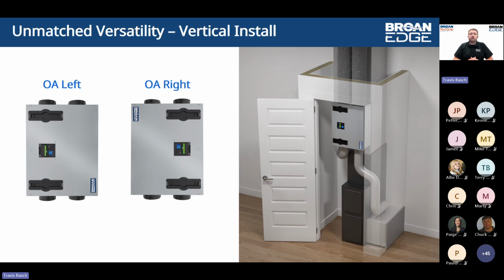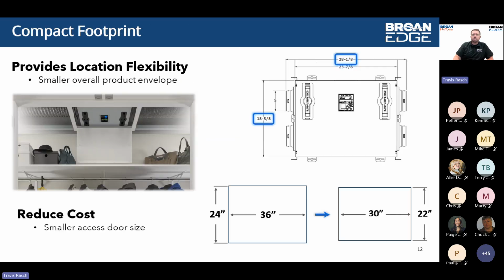Again, be looking at the fan curve charts, understand what additional static pressure you're going to be adding to the system by having those types of designs, and just manage expectations when it comes to that overall CFM output of the product. We're showing it here. We've done validation testing of this type of configuration, making sure that if we're going to have those immediate elbows or number of elbows, etc., and I'll highlight it during the virtual piece of this presentation. We're fully mindful of that, and so we've done the validation testing to ensure that we limit some of that feedback that you provided, Craig, in your question there. Hopefully that answers your question.